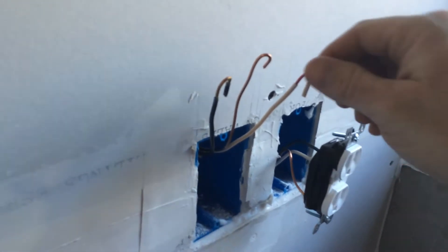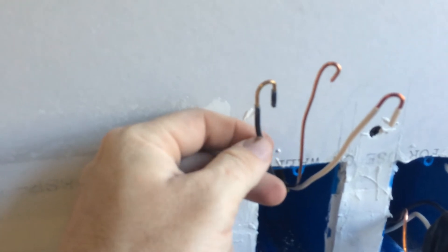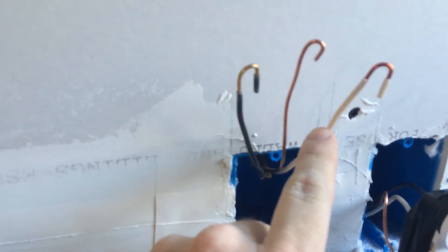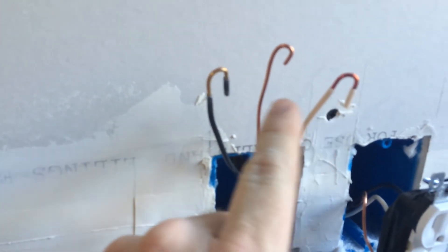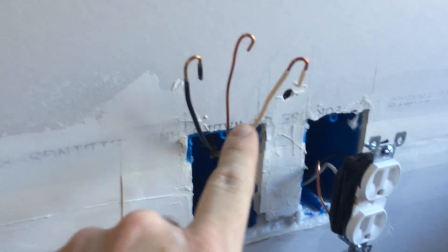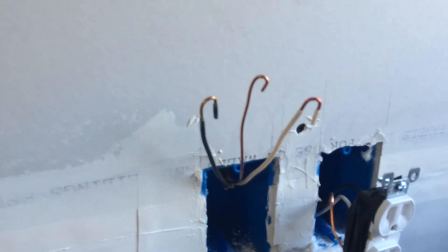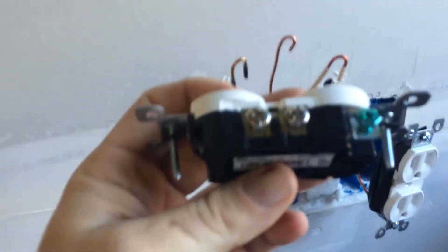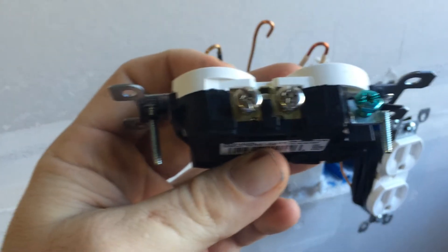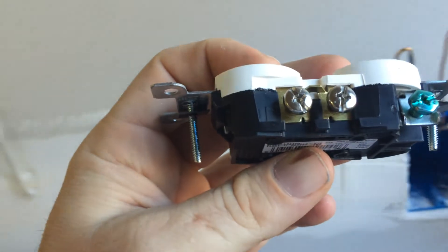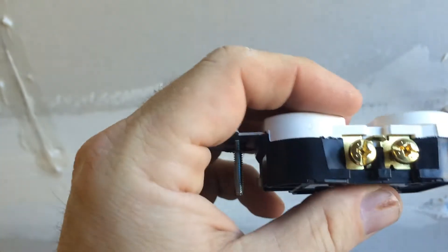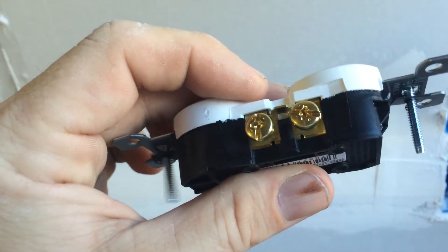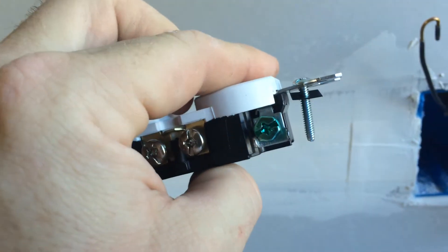You see how the wires are set up - you have your black hot wire, ground wire, neutral wire or grounded wire. Don't let me confuse you too much. White wire goes on the silver screw, black wire goes on the brass one, and then of course ground goes on the green screw.